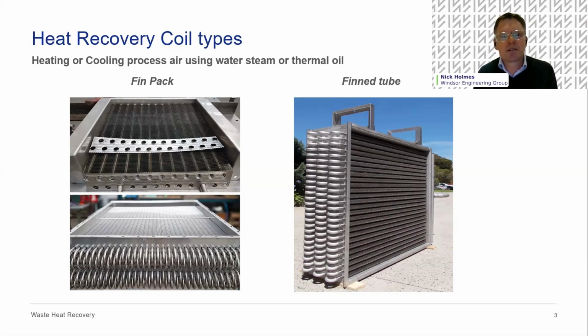So probably the key bits of information to consider when you're designing a coil is what is the exhaust stream or the waste stream that you're looking to recover. Has it got particulate in it that might foul up a heat exchanger? Has it got chemicals or acids that could corrode the materials? So material selection is key to that. What sort of back pressures can it accommodate? If you've got a sensitive process like a reciprocating engine, they're very sensitive to having additional back pressure on them. So you may struggle in certain applications to put a coil in that kind of scenario. And what are the temperatures that you're trying to achieve in the fluid? In this instance, if you're recovering exhaust gas, putting it into hot water, what are the peak temperatures of the exhaust? The closer you get to the pinch temperature of the fluid, the harder it is to recover that energy. You need more heating surface, and it's diminishing returns. So there's always a sweet spot of the design.